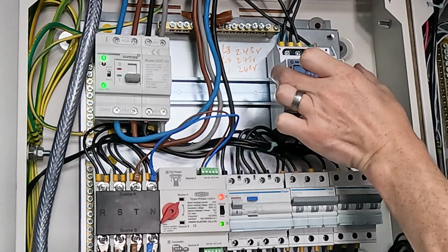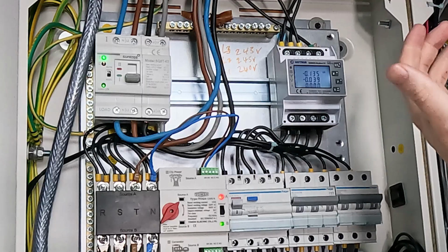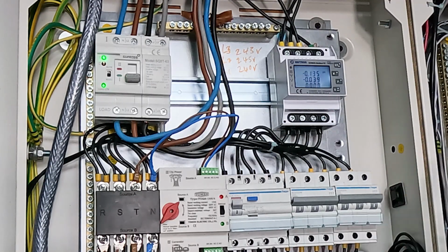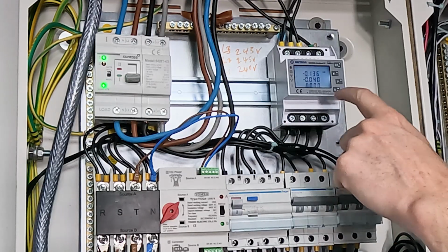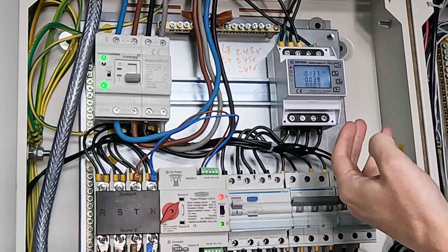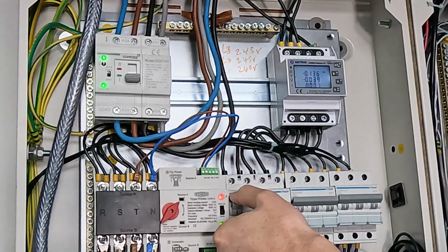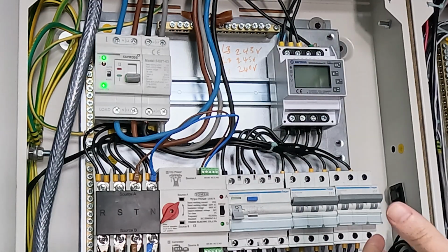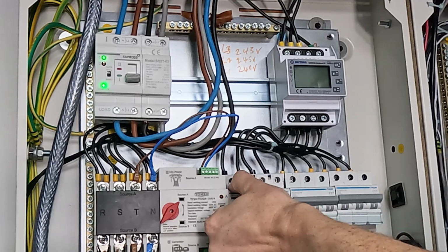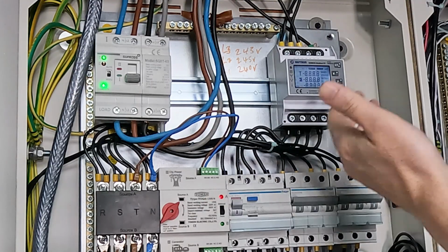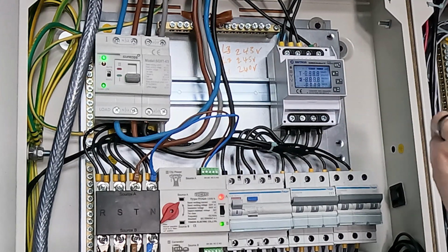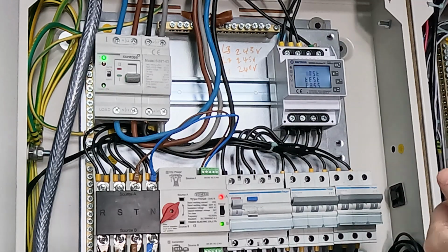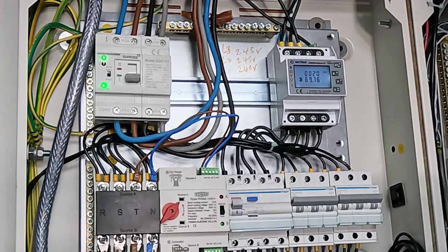So this main breaker is feeding a distribution board that could be labeled my non-critical loads. Then to the right of that, I've got a three-phase meter, and I've just got that in my board here to symbolize when the voltage is present on my backup circuit. So this is a meter feeding my critical circuits, and when I turn off my critical circuits, the meter gets no power and the LCD is off. So it's a very good indicator for this video of when my voltages are present on my backup and how fast my backup transfer is. If it's a very slow transfer, the LCD turns off.